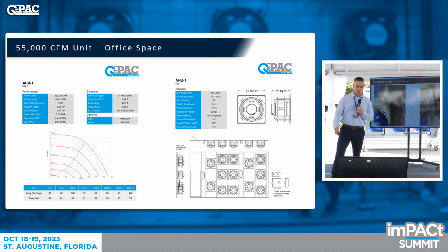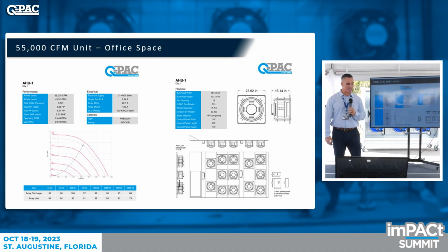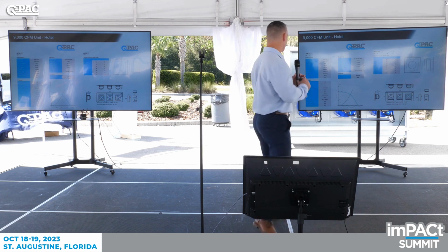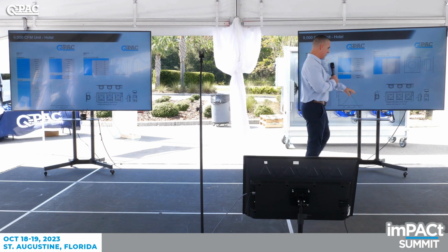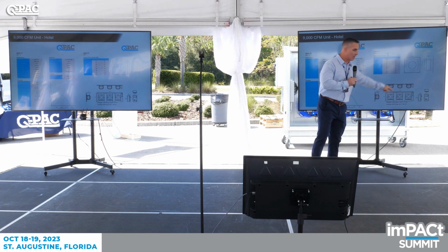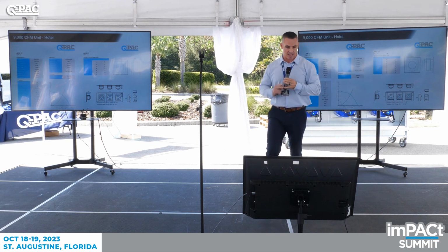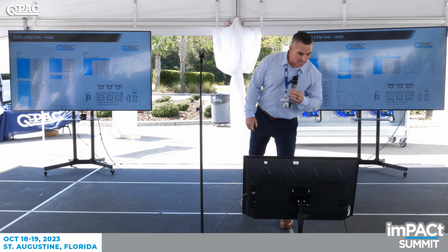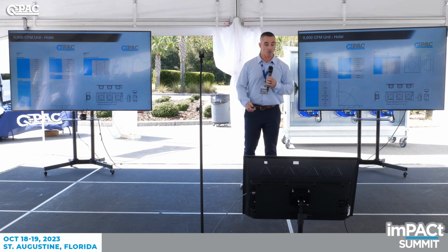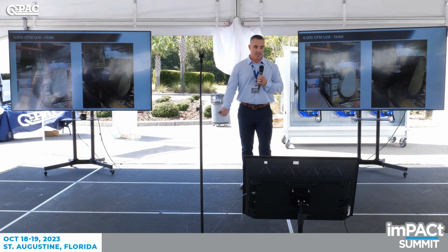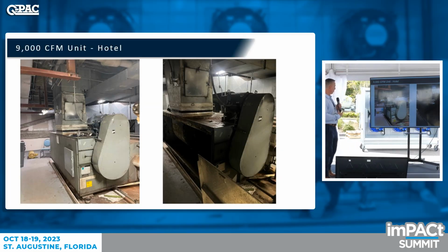So my last example is one of my favorite ones to show. It's only 9,000 CFM. The bulkhead wall, you can't see it, but it's 34 inches by 100 inches. We're at 9,000 CFM, 4.5 inches. This is at a hotel, and this is the unit before.